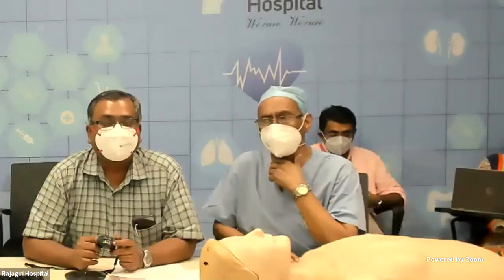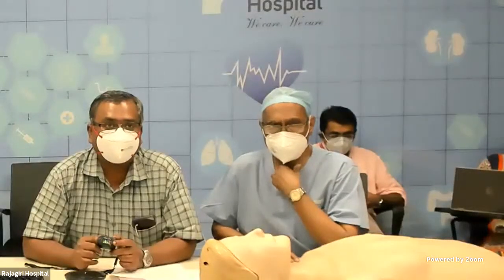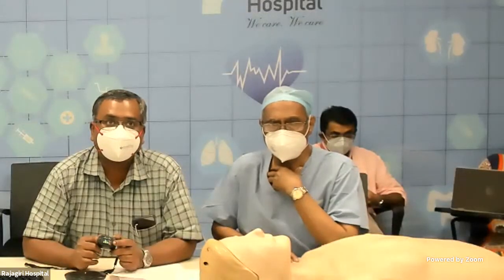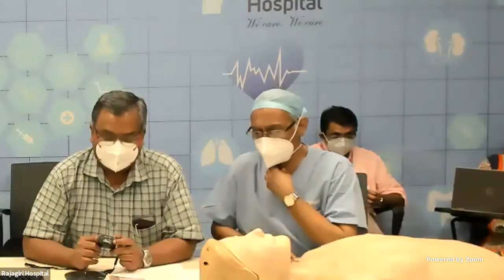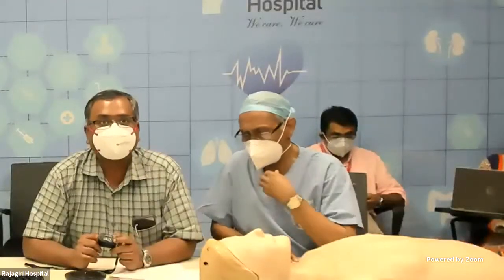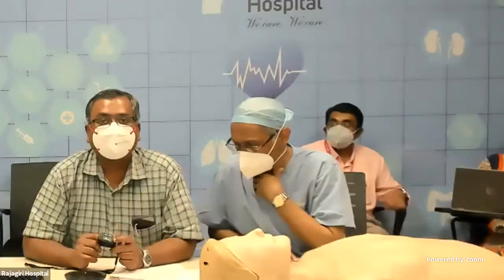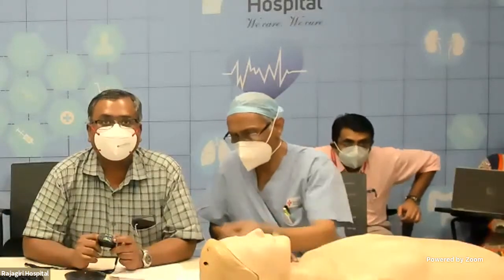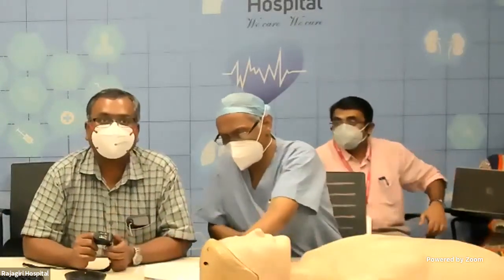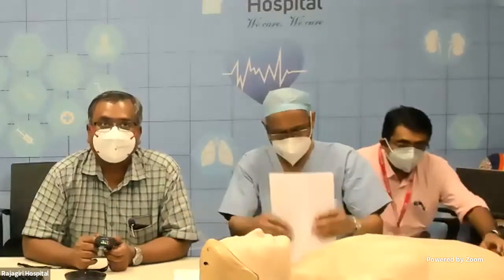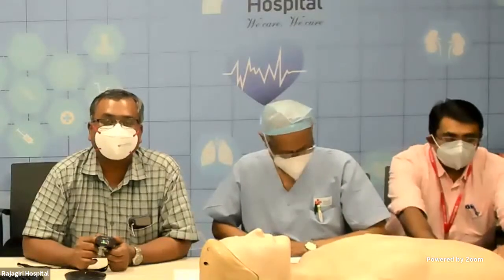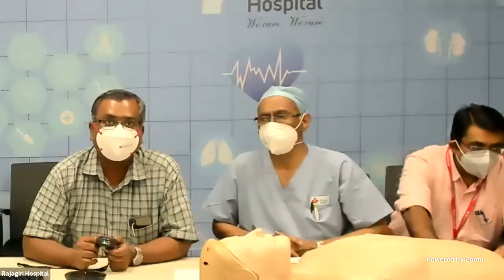The usual waveform will have something similar to an arterial waveform. Arterial waveform, you would all have seen, there will be a peak, a small dicrotic notch and a dip. So the pulse oximeter waveform will also have something similar. If you have a uniform, very synchronized waveform, then most likely your reading is correct. If the waveform is not corresponding to the heart rate, or if the waveform is not uniform, or if the peaks are not uniform, the reading is unlikely to be correct.